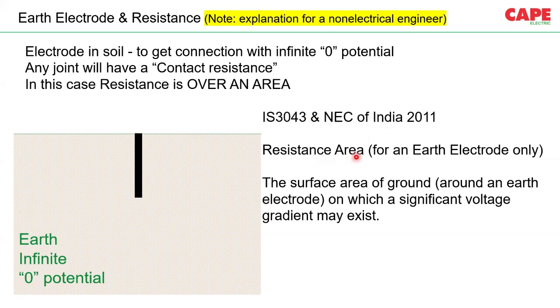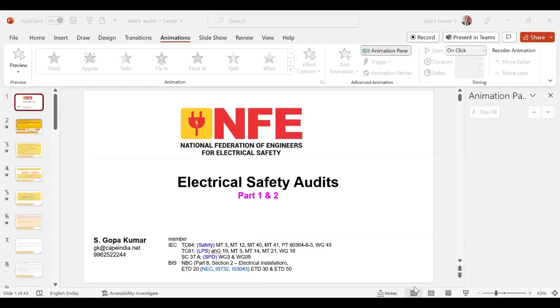A resistance area, for example, the definition for an earth electrode only. You should always read it this way: earth resistance area for an earth electrode only, the surface area of ground around the earth electrode on which a significant voltage gradient may exist. What I will do is show you how this is written in the standards IS 3043 and IS 732. I'm sure you are able to see the screen. I'm showing you NEC, National Electrical Code. Okay, before that, I'm showing you IS 3043. All of you know very well it is the code of practice for earthing.